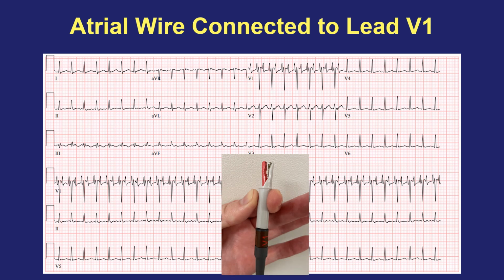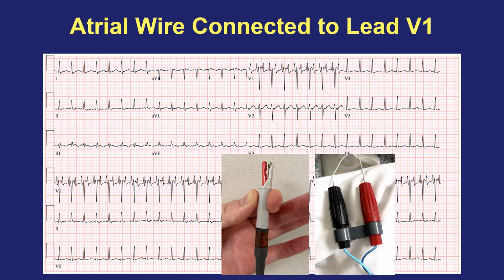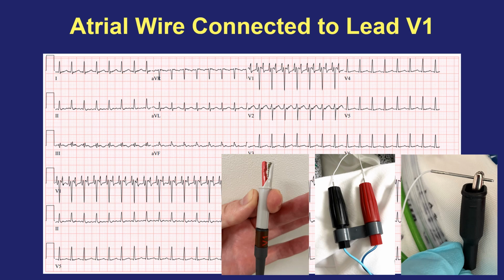Here is how you would perform that. The V1 EKG electrode, depending on the model of EKG machine that you have, is usually some type of clip that normally would hook up to a tab or an electrode on the patient's body. But instead here, you can take one of those wires. Again, remember in our system, we use the white wires by convention for the atrial wires. You can take one of those and connect it. This is a different type of alligator clip. Sorry, I don't have a picture of hooking up the EKG electrode to it, but basically it's the same thing. And now you've established electrical continuity between this epicardial atrial wire and the EKG machine, and it'll give you this type of recording and make it crystal clear what's happening in the atrium.